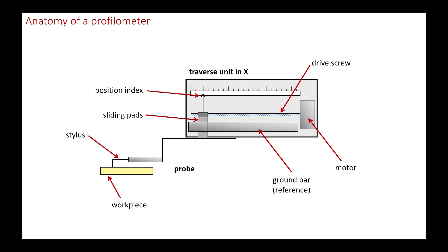It allows the stylus to record the entire surface texture, be it roughness, waviness, form deviations, or even the form itself.